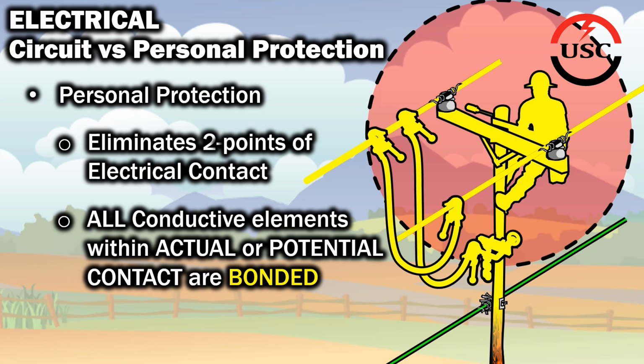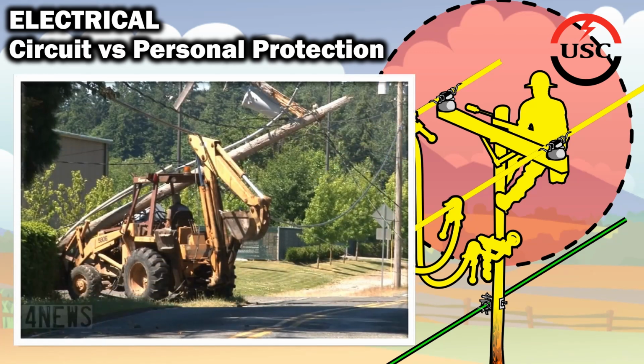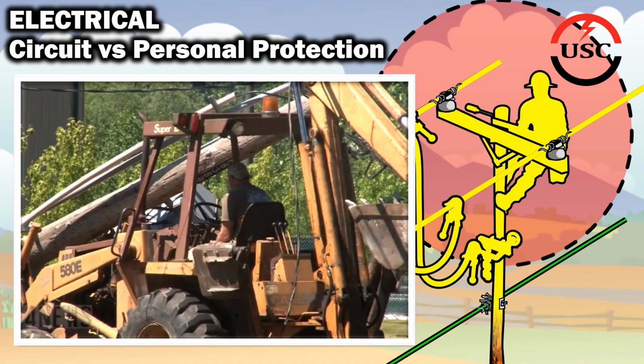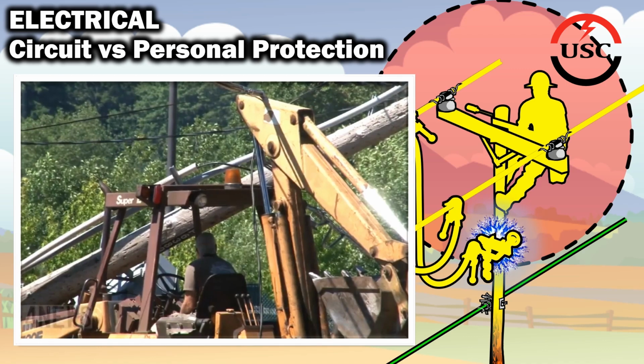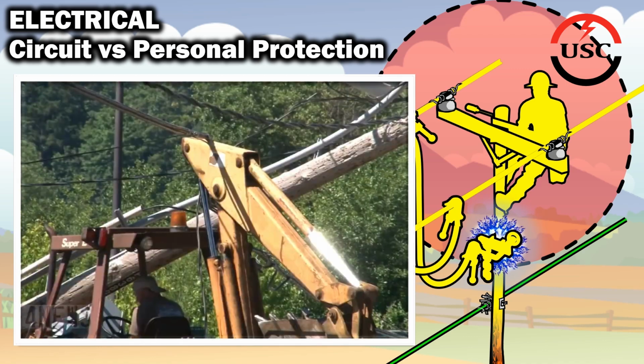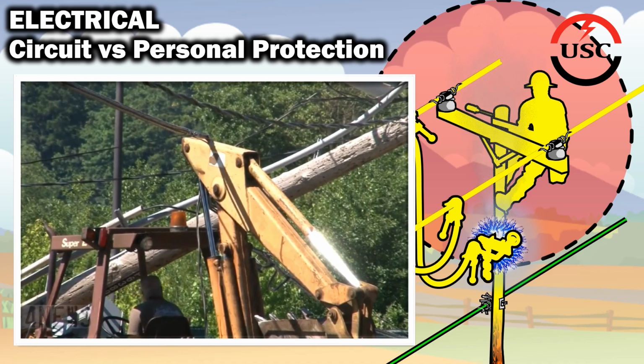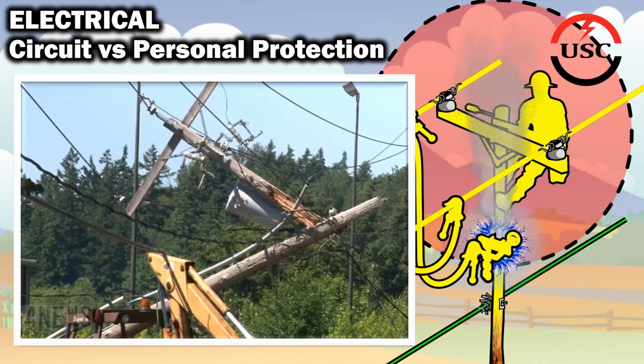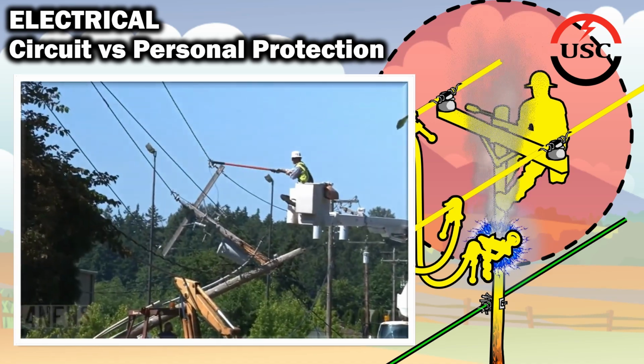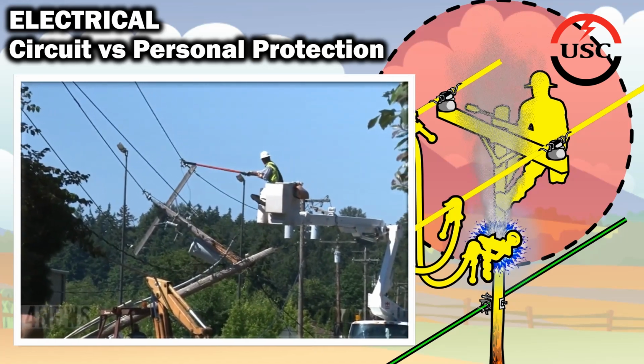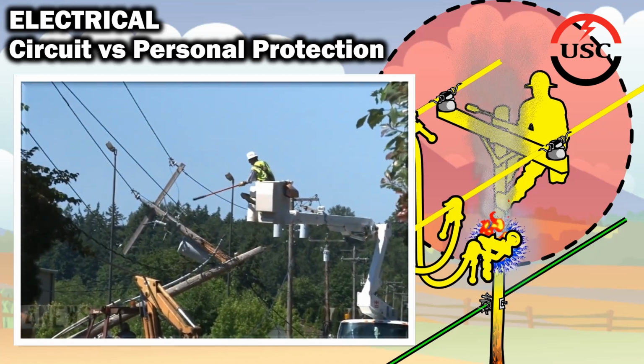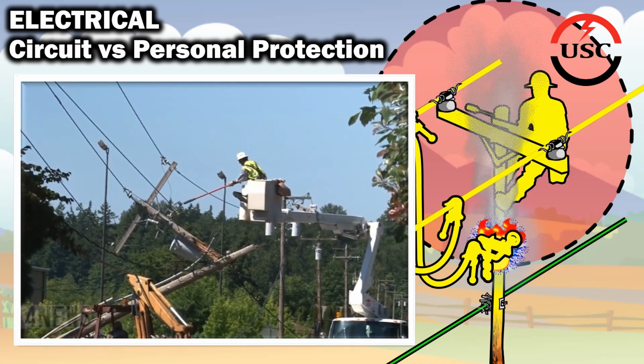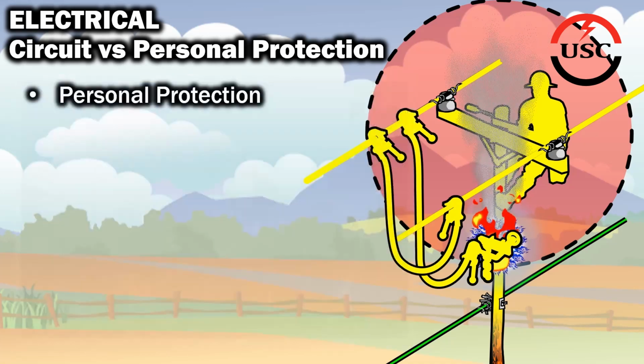Personal protection does not necessarily require a direct connection to an effective ground, although it is very highly recommended. If personal protective grounding is not bonded to an effective ground, then although the worker may not be exposed to 2 points of electrical contact, the fault may very well continue unabated, thereby trapping that worker at his work location. A practical example of this exact scenario are those cases where you can see operators stranded on their equipment that has made contact with an energized source. They are in an equipotential zone of protection, but they can't leave.